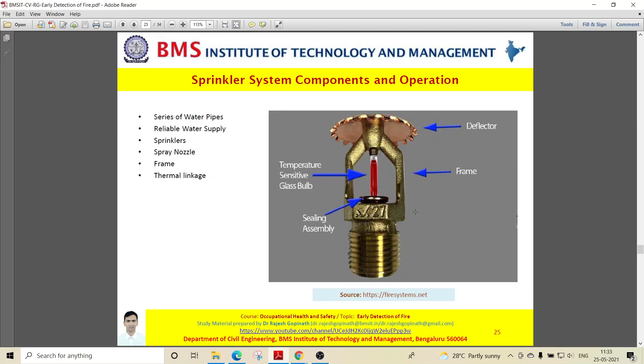Apart from this, what you basically see on your screen is a frame. It could be a metallic frame or of any other make. Basically the frame is your structural component - it is that component which holds the sprinkler together. Finally we also have the thermal linkage. This is the component which controls your water release, by a mechanism where, when the heat rises, this system is responsible for releasing water and dousing the fire. Of course there are deflectors and caps too, but I won't delve more into that.